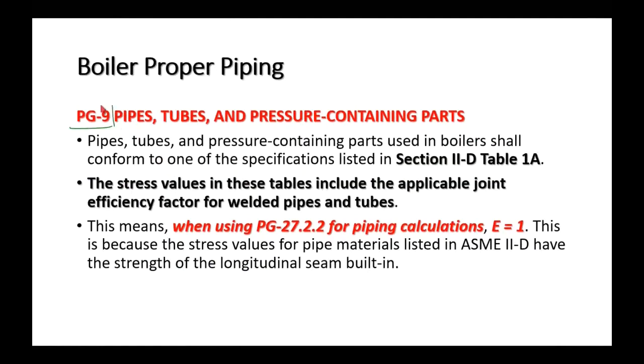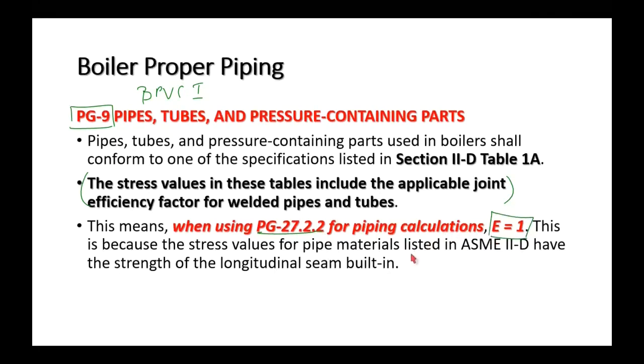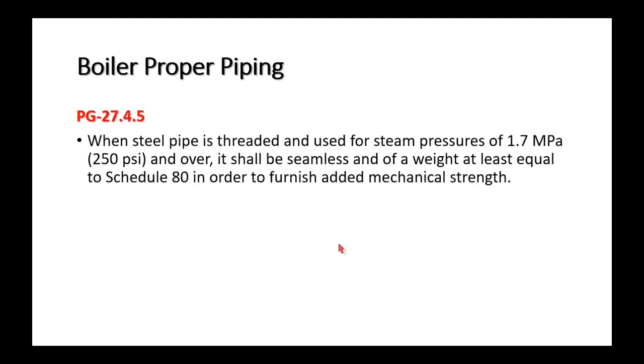PG-9 in BPVC Section I says pipes and tubes shall conform to one of the approved specifications, and that stress values in the tables include the applicable joint efficiency factor for welded pipes and tubes. So when using PG-27.2.2 for piping calculations, E must equal 1 — the penalty for the method of pipe construction is already built into the stress values.